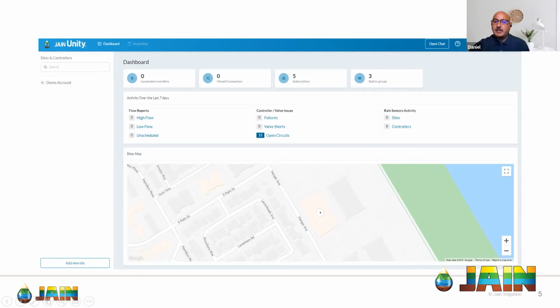So one thing our system does is it has two-way communication, right? We've got cell phone modems in there. Not only are we able to send a watering command or connect command to controllers, they report back what's going on out in the field. If the controller notices a valve issue, failure, or flow problem, you'll get it in this little notification box. Click on there, and the system will tell you exactly what happened and when it occurred. And then you can log into your account here, change your password, update your email or phone number in case we need to send any correspondence your way.